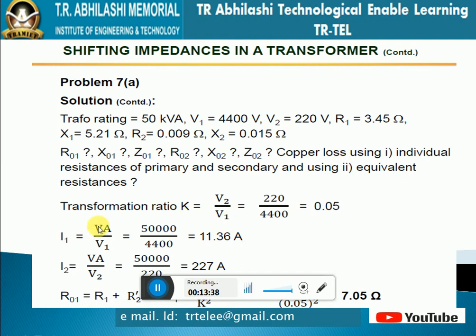What is I1? That is VA upon V1. What is VA? That is 50 kVA. kVA means it contains voltage as well as amperes, so if we divide by V, what remains is current. You will find the value, that is 50 kVA upon 4400.